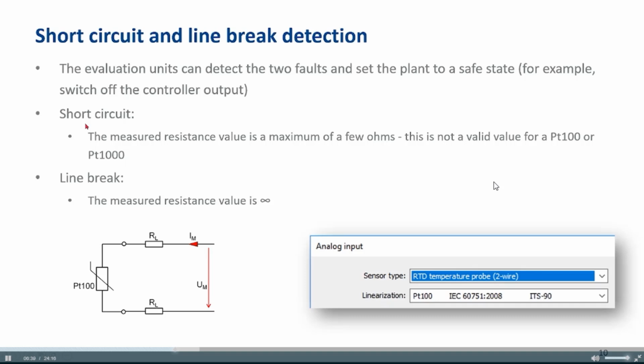Let's say if you have a short circuit, then maybe you have 1 ohm or a few ohms, something like this. It depends on the length of the cable. But the device then measures the ohmic value. The ohmic value is less than what you can expect with a PT100, PT1000, and the evaluation can detect this error. The device can see, oh, there's an error. And if it's a controller, for instance, then the controller can switch off its output. It goes to the safe status.